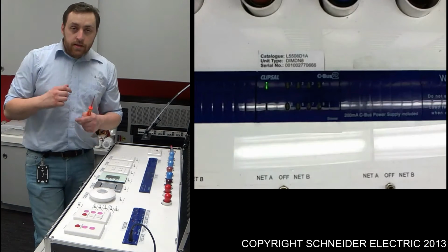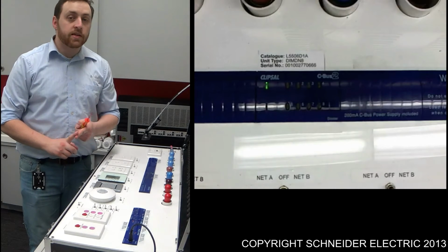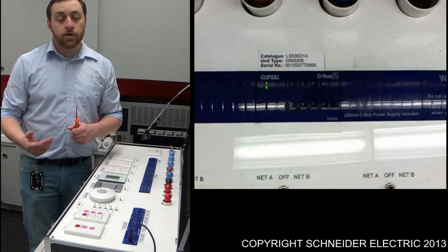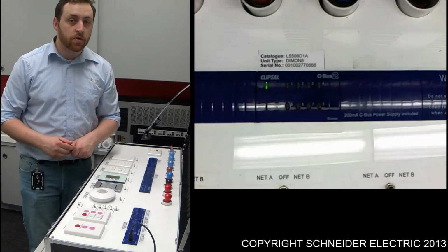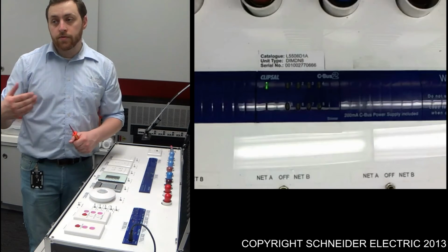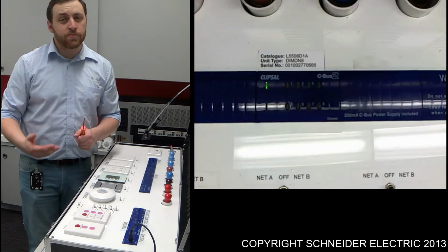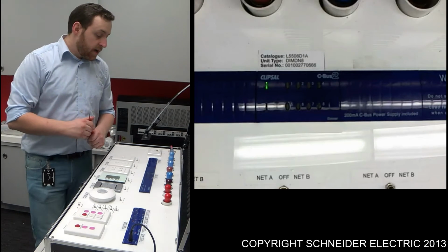That can be caused by one or two things. The first one is that there's no CBus power. Now you'll typically know whether that's going to be the case because you'll just remember at this particular point, hang on, I haven't installed any power supplies, or you don't have enough power supplies. So you'll know that one pretty much straight away, and that's something that you should be picking up during the design phase of your installation.